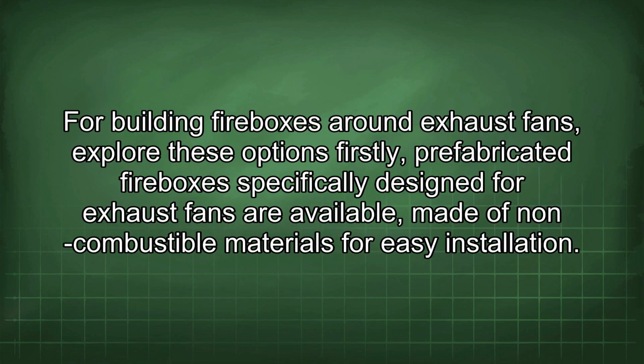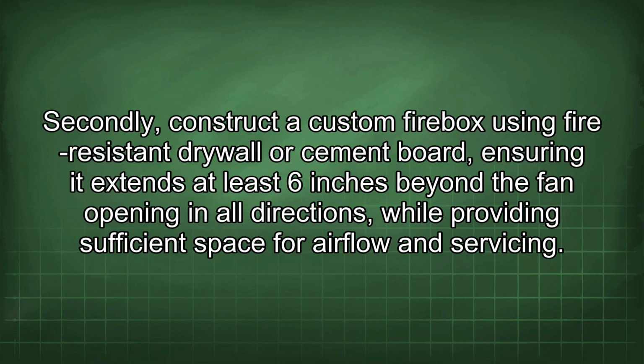For building fireboxes around exhaust fans, explore these options. Firstly, prefabricated fireboxes specifically designed for exhaust fans are available, made of non-combustible materials for easy installation. Secondly, construct a custom firebox using fire-resistant drywall or cement board, ensuring it extends at least 6 inches beyond the fan opening in all directions while providing sufficient space for airflow and servicing.